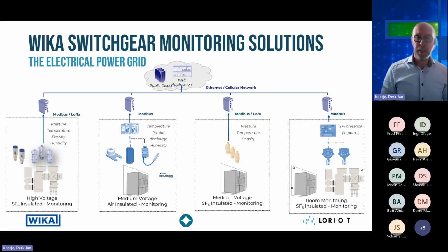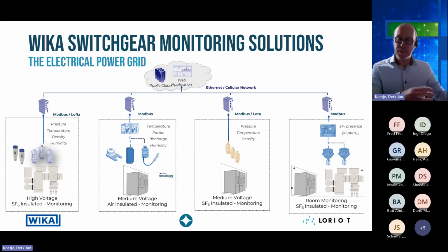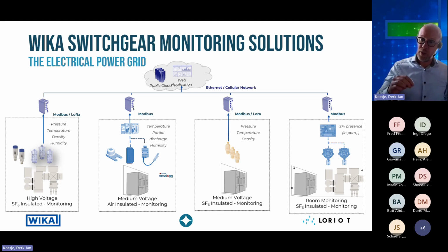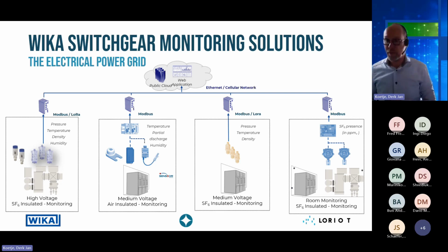And the fourth monitoring solution we offer is room monitoring of SF6 gas, because in some cases you have an indoor gas insulated switchgear. The room monitoring literally detects any leakage of SF6 gas in the enclosed environment where the gas insulated switchgear is installed, so we can be sure it is safe for technicians or other people to go inside this closed environment.